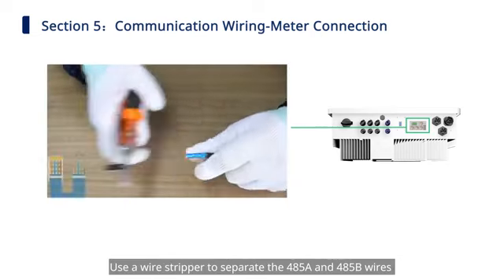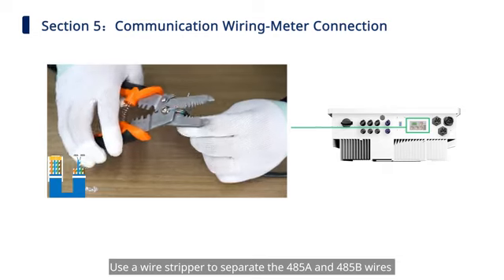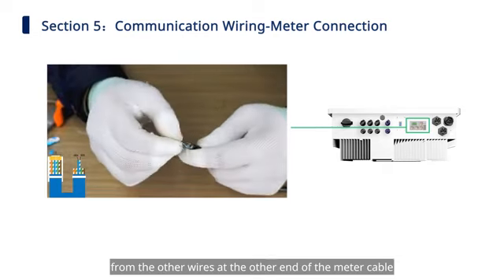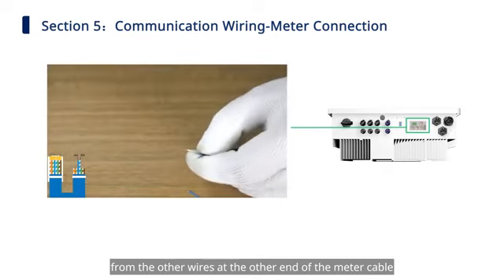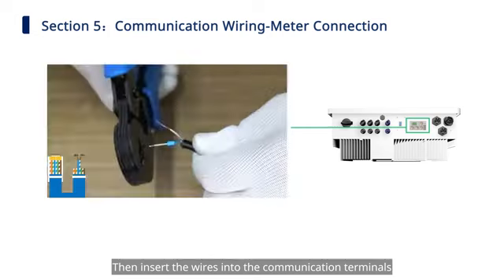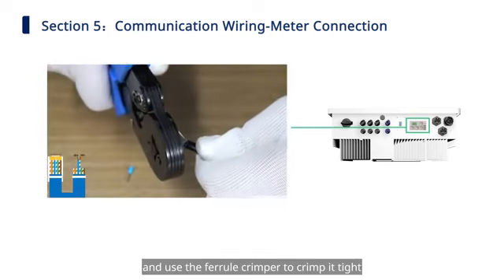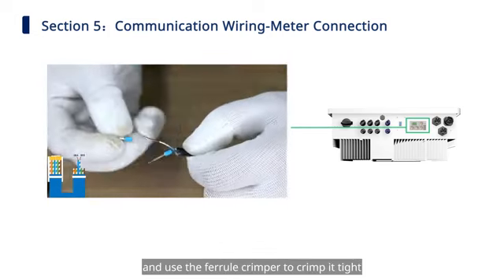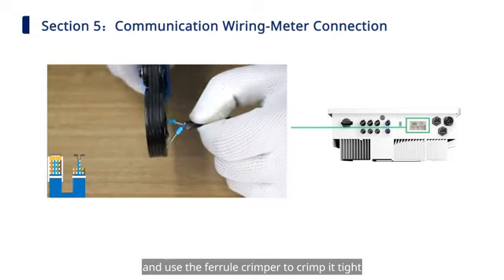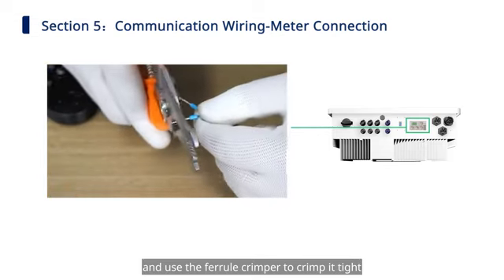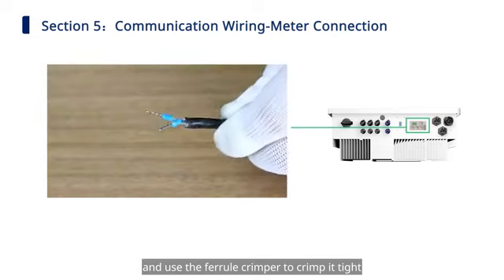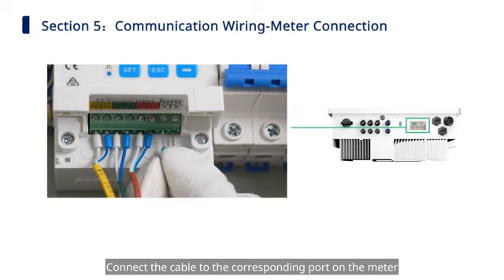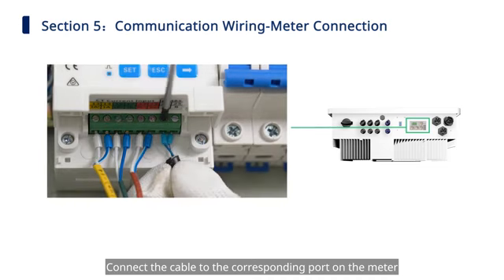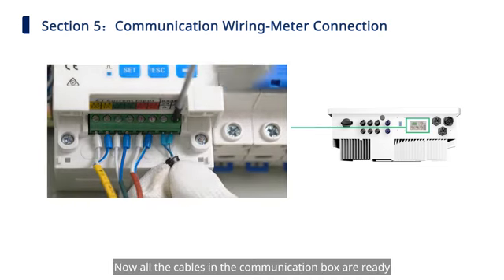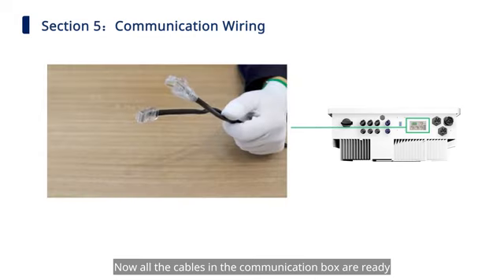Use a wire stripper to separate the 485A and 485B wires from the other wires at the other end of the meter cable. Then insert the wires into the communication terminals and use the ferrule crimper to crimp it tight. Connect the cable to the corresponding port on the meter. Now, all the cables in the communication box are ready.